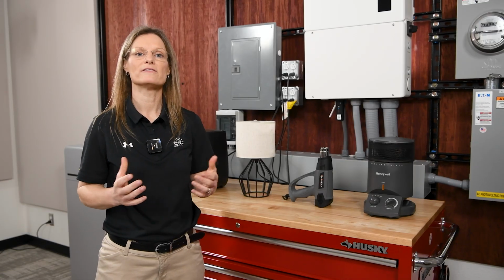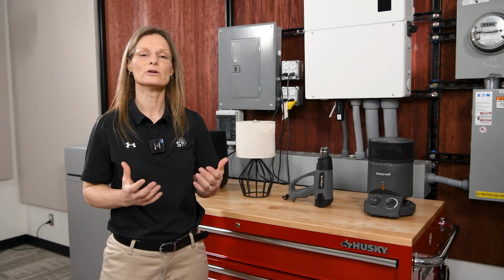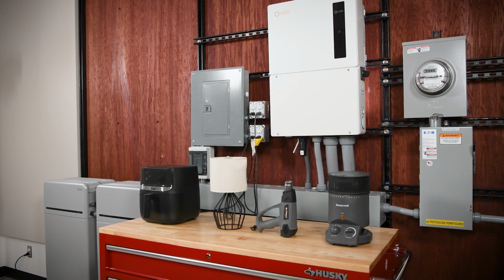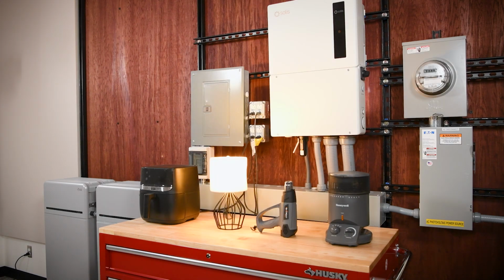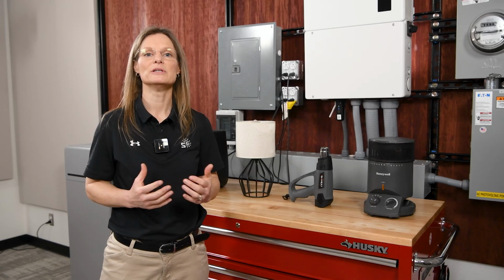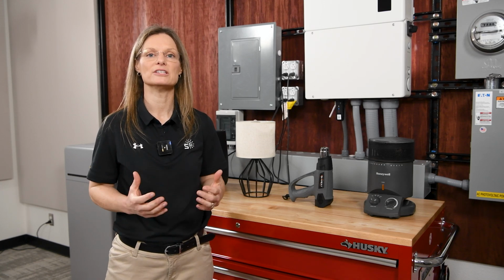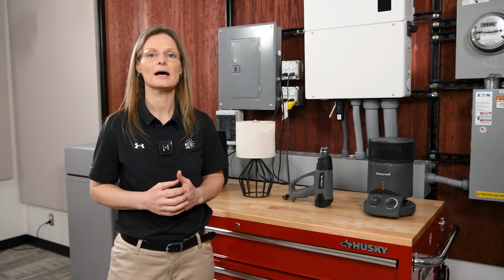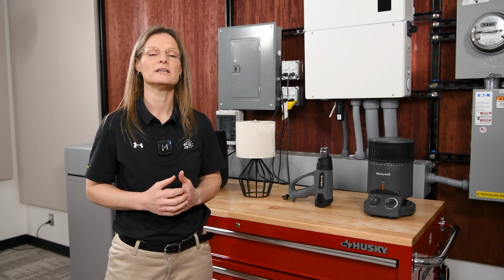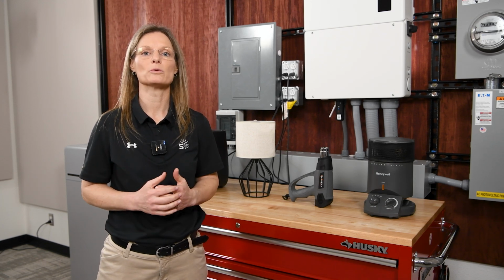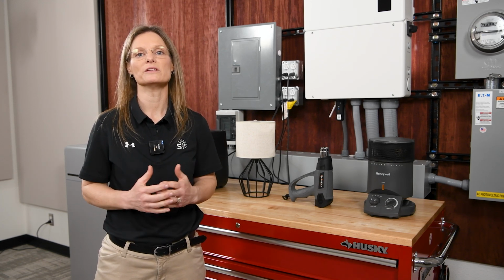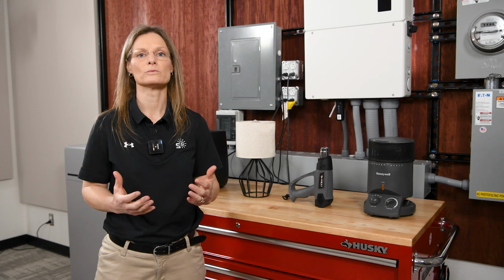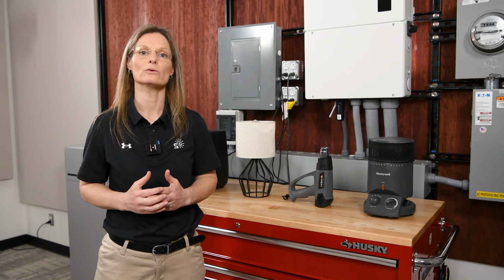It'll take about 5 minutes for this to turn on. You'll know it's turning on when you hear a series of clicks. If you don't hear clicks and it doesn't turn on, be sure to go to the Solis Cloud app and check the alarm page, which we'll look at shortly, to determine if there's a problem with your inverter and what the alarm is, or reasons why it may not be coming all the way on.